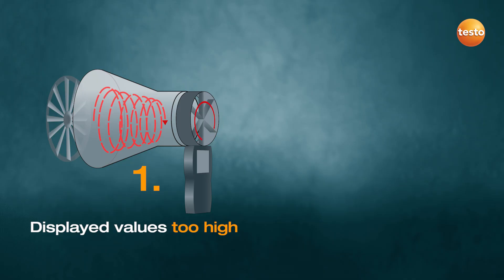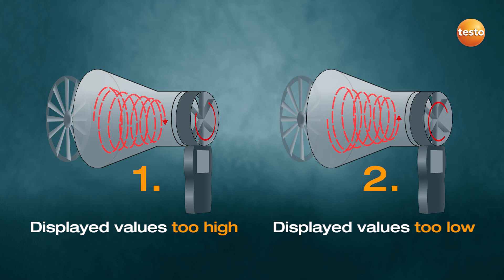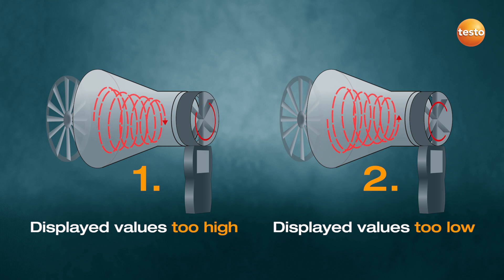Let's take a closer look at what happens. First: the direction the swirl rotates is the same as that of the vane. What happens? The flow hits a larger cross-sectional area of the individual blades of the vane, making it accelerate too fast. Second: the direction the swirl rotates is the opposite to that of the vane. What happens? The flow passes between the individual blades of the vane, meaning it doesn't accelerate properly.